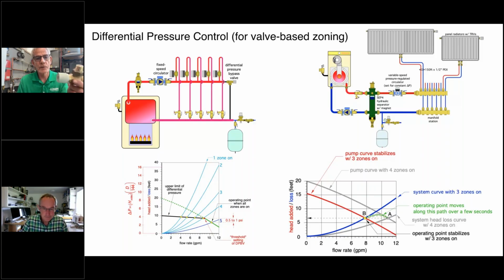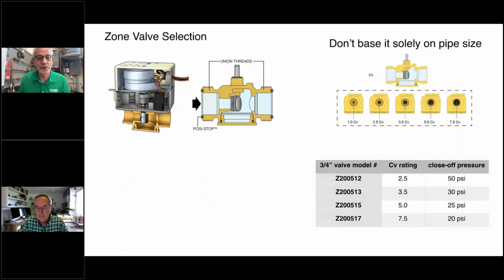And we still offer that valve, by the way, a differential bypass valve. It's got the PSI settings on it. And I mean, simply just a valve, you can see just a spring and a disc in there that opens up. So if you come across a system like that has problems and you don't want to change out a pump, we can still sell you a differential bypass valve. So we're going to switch. We're going to look at zone valves, and I know Hot Rod has got some valves to show you here.